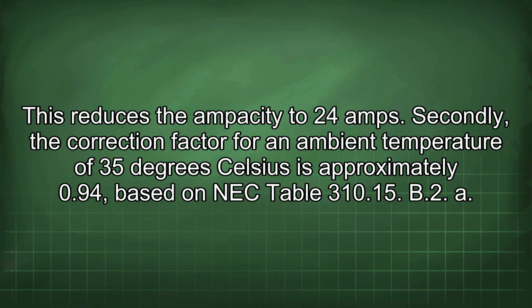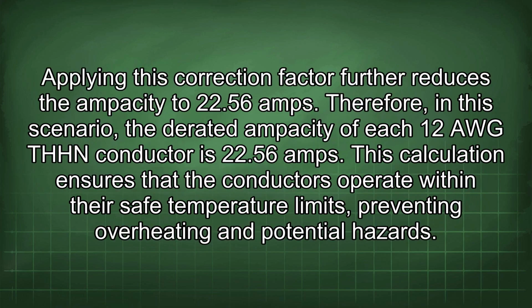Secondly, the correction factor for an ambient temperature of 35 degrees Celsius is approximately 0.94, based on NEC Table 310.15(B)(2). Applying this correction factor further reduces the ampacity to 22.56 amps. Therefore, in this scenario, the derated ampacity of each 12 AWG THHN conductor is 22.56 amps. This calculation ensures that the conductors operate within their safe temperature limits, preventing overheating and potential hazards.